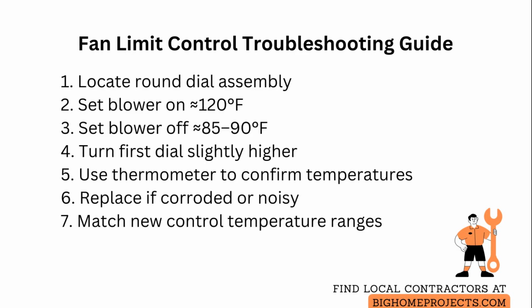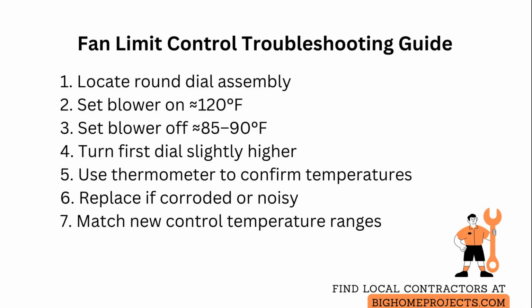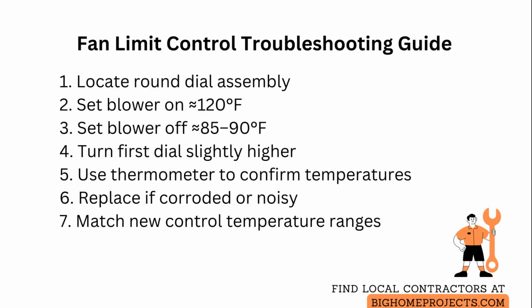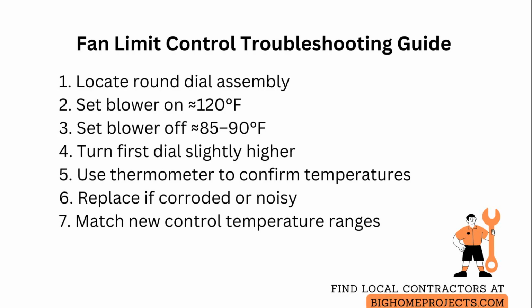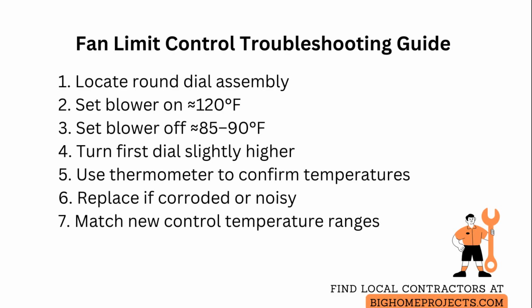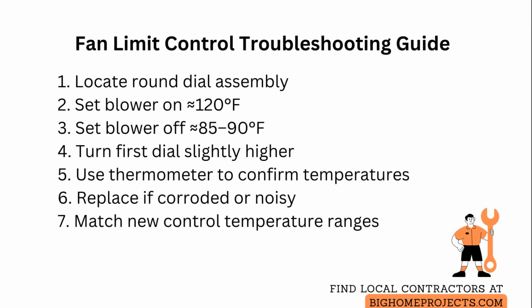Use a refrigerator thermometer or an infrared thermometer aimed at the heat exchanger casing to confirm actual surface temperatures if you need precision without removing panels. If the control is noisy, shows physical corrosion, has loose wires at the terminal block, or the dials move without resistance, the mechanism is likely failing and replacement is the correct course.